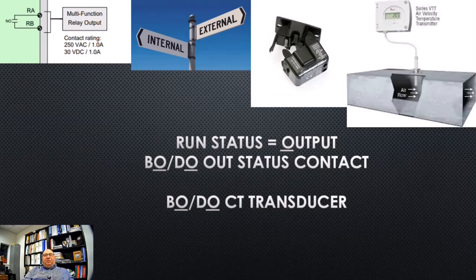Now, we're going to need to know, is the drive running? Okay, we need to have a status. Is the drive running? Okay, so we could use the internal relays on the drive, or we could put external devices in. All right, so I highly recommend using external devices. The reason being is it frees up this multifunction relay output, because we could use this as an alarm or an alert output. If we use it as a fan status or a status point, we take it out of use, whereas it's more important to use it somewhere else.